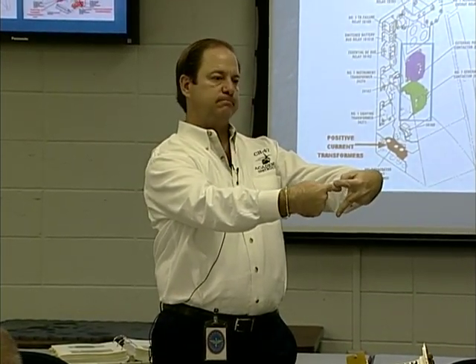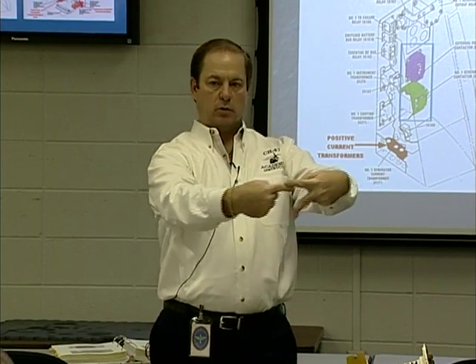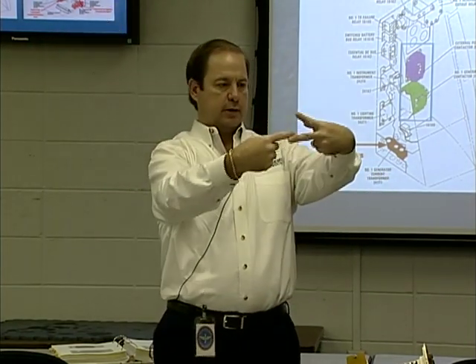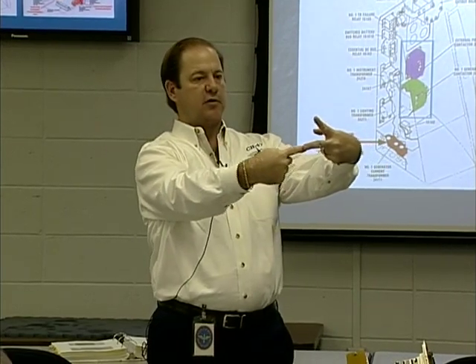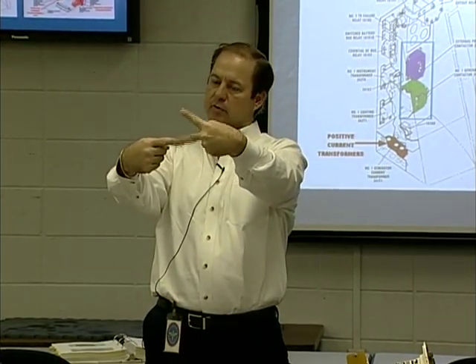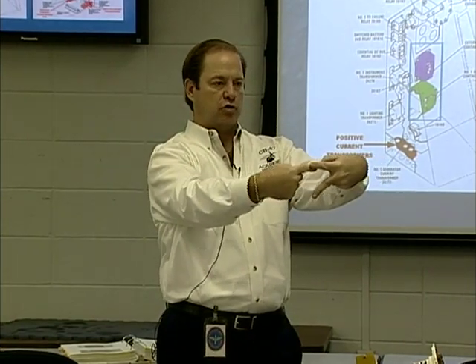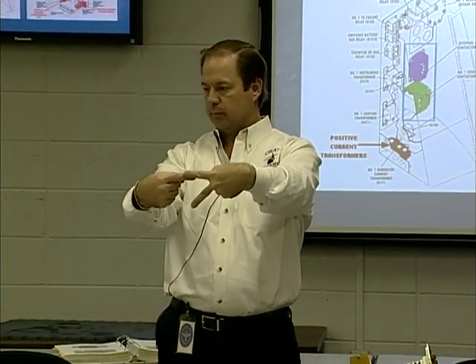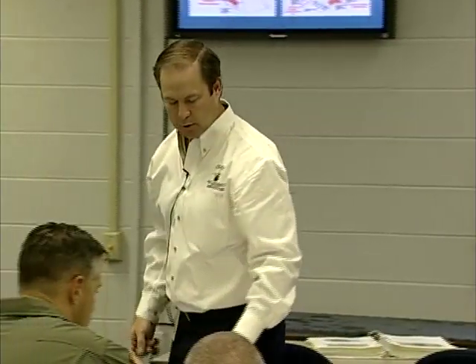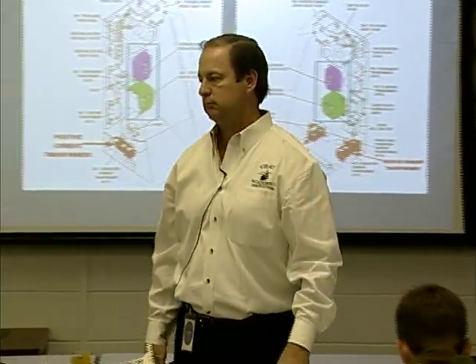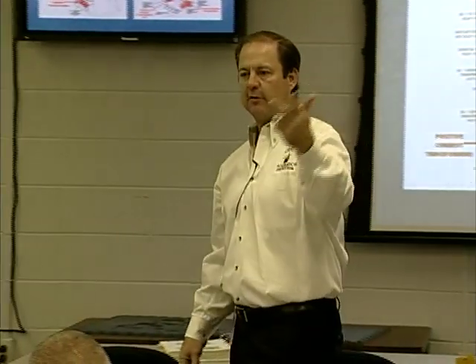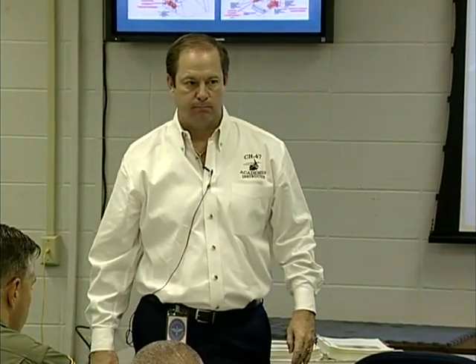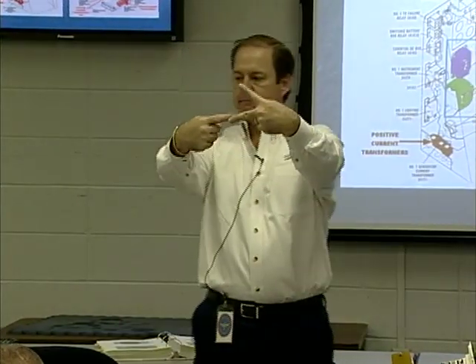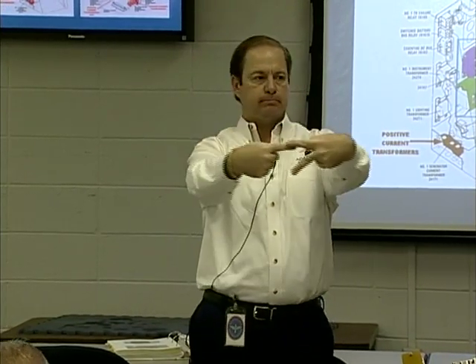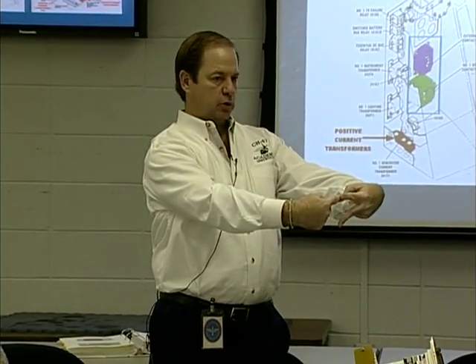And it's going to switch, turn on the number 2 generator, and the same thing's going to be allowed to happen. Instead of using the APU generator through the automatic bus tie system, it's now going to use its associated generator. We good? Okay, so now here we go. The generator control unit says, hey, number 2 generator's not working right, either an over voltage or under frequency, it's irrelevant. What's going to be allowed to happen? Boom. Good?